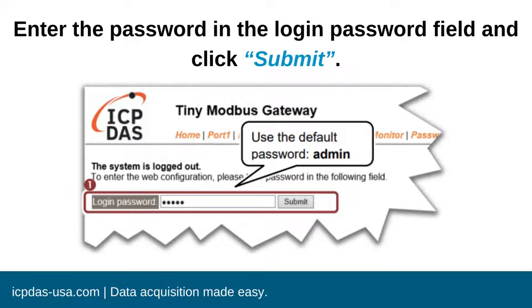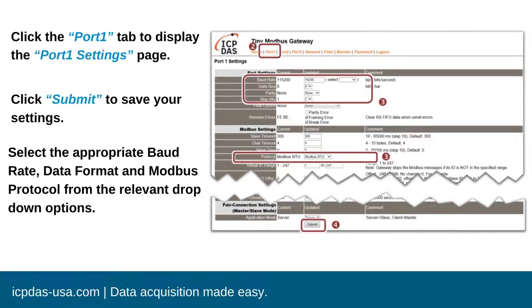To configure the serial port, enter the default password and login. Click the Port 1 tab to display Port 1's settings page. Select the appropriate baud rate, data format, and Modbus protocol from the relevant drop-down options. Please note these settings will vary depending on your Modbus device. Save your settings by clicking Submit.